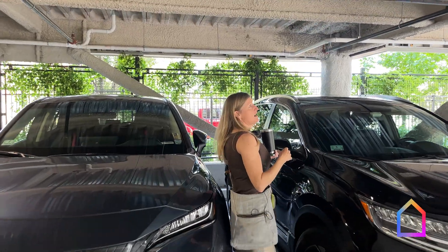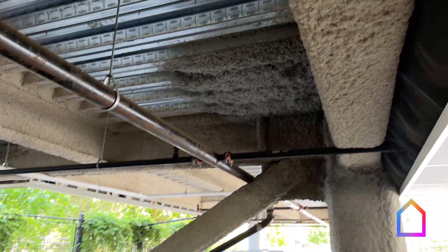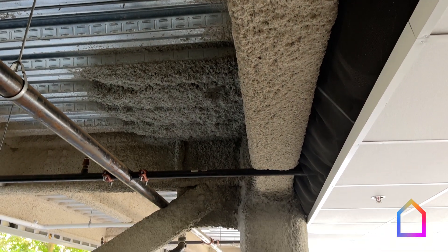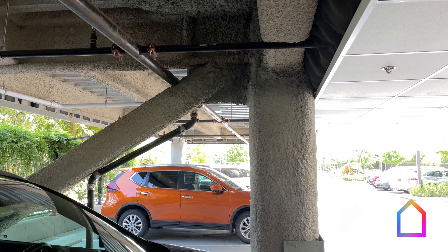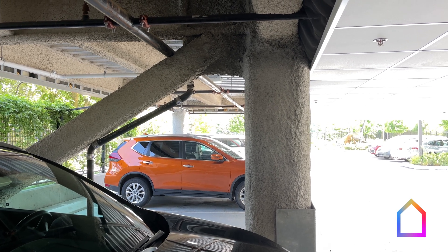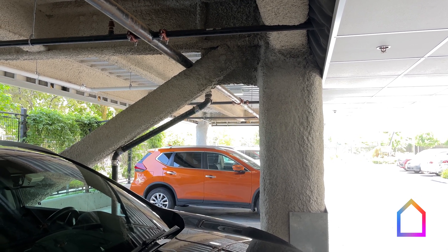We did a lot of analysis of the dew point and ultimately evaluated that if we oversprayed a certain number of feet in either direction around the column, it got just enough so that we didn't have a risk of condensation on the floor inside. But it was an analysis during construction that we wish we hadn't had to do. Now our structural engineers know — they'll ask, isn't that a thermal break? Do we need to address it? Yes, it is. Yes, we do. So we're all learning.